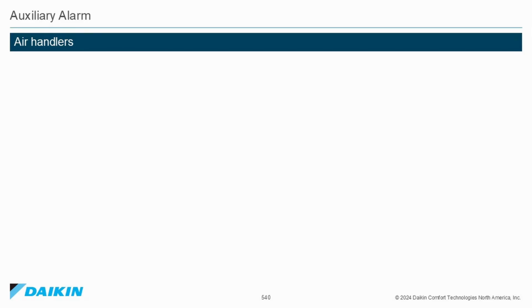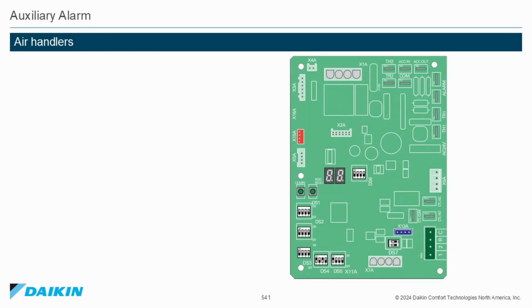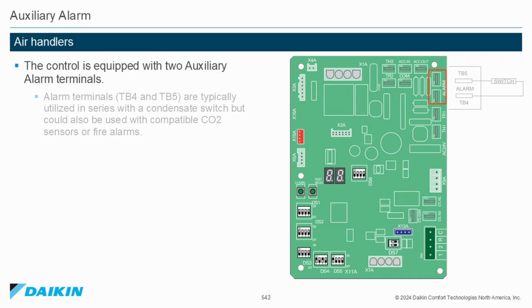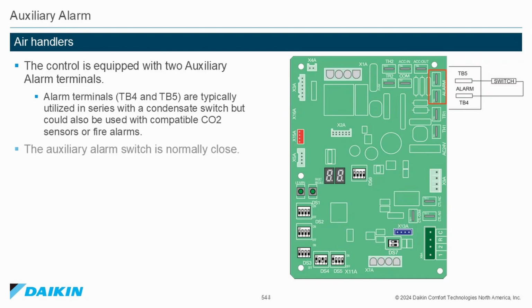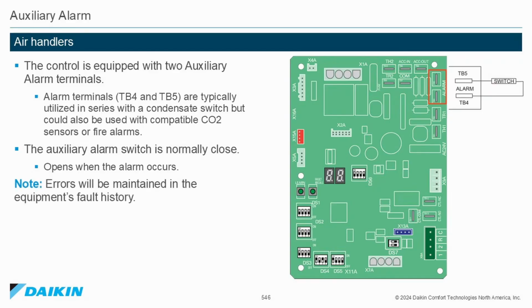Auxiliary alarm, air handlers. The control is equipped with 2 auxiliary alarm terminals. Alarm terminals TB4 and TB5 are typically utilized in series with a condensate switch, but also can be used with compatible CO2 sensors or fire alarms. The auxiliary switch is normally closed. It opens when the alarm occurs. Note, errors will be maintained in the equipment's fault history.